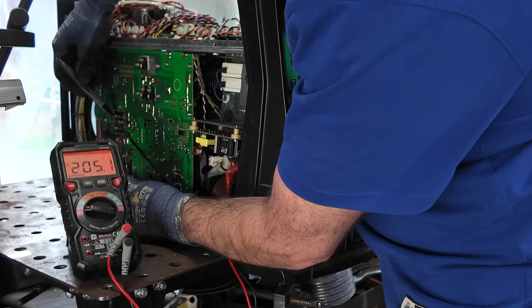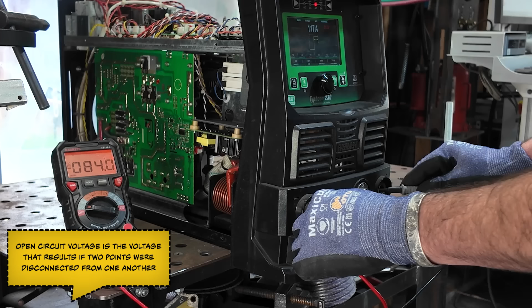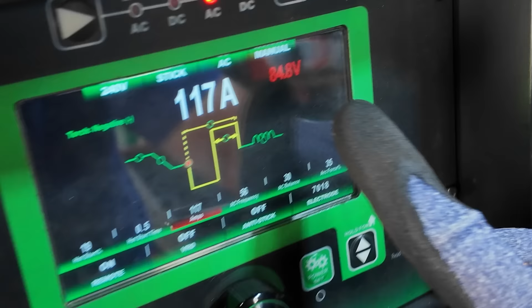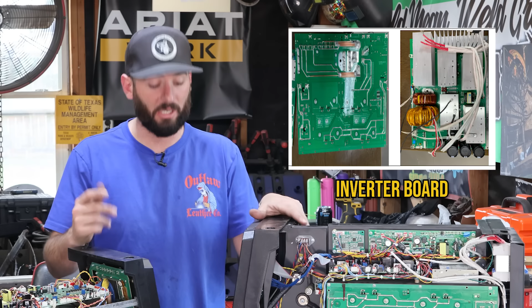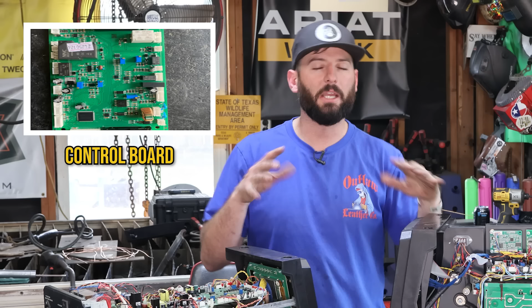One good reason why you might want to use one of these voltmeters is to check if you have open circuit voltage. That could be a really good starting point to troubleshoot your welding machine. All you really do is turn the voltmeter on and start sticking it in the terminals where power should be coming from, and you should see open circuit voltage coming from those terminals. That's your output right there. If you don't have that open circuit voltage, it could be maybe the inverter board, something wrong with it. But if you do have open circuit voltage, it might be something to do with, I don't know, maybe your control board. Again, things to consider. Keeping a voltmeter when it comes to troubleshooting your welding machines is one of those tools you kind of need to have.